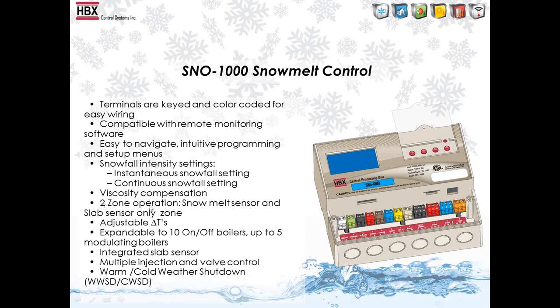Has things like viscosity compensation, 2-zone operation, so it has a slab zone and a snow zone. Adjustable delta T's, so you can adjust boiler delta T's and system delta T's. Can go up to 10 on-off boilers or 5 modulating boilers. Obviously the slab sensor is integrated into the SNO-1000, warm weather shutdown, cold weather shutdown, and multiple injection or valve control. So we can do injection, pumping, we can do three-way, four-way valve injection, modulating injection. So there's a lot of different opportunities for different snow melt systems.